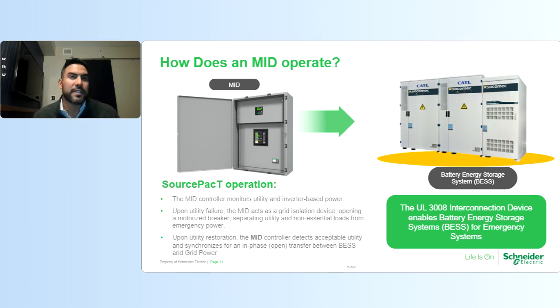Now, why is it important to separate your non-essential loads from utility power? These energy storage systems have a finite amount of capacity. So when you experience an outage, you already want to have your facility designed so that your essential loads, the ones that require emergency power, are separated from the non-essential loads. So your energy storage system could provide at least 2 hours of runtime and specifically provide backup power to those specific loads without dispersing energy throughout the entire facility for loads that don't require that emergency power.